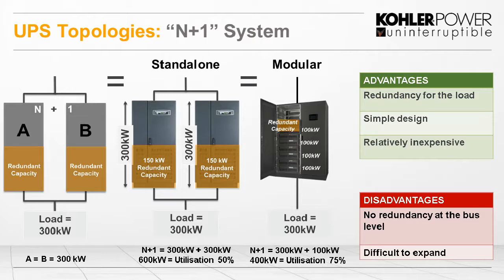It is still a relatively simple design, especially on the modular when it's got one input, one output. And again, it's probably the most inexpensive way of getting a redundant system. Okay, but the disadvantages are that the load is only fed from one bus. So if that one bus goes down, we have no protection. And again, if not designed properly from the start, it can be difficult to expand.